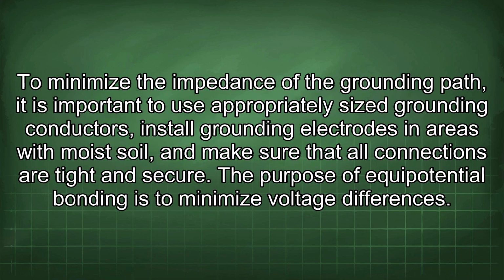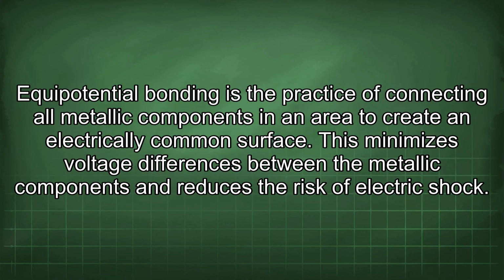To minimize the impedance of the grounding path, it is important to use appropriately sized grounding conductors, install grounding electrodes in areas with moist soil, and make sure that all connections are tight and secure. The purpose of equipotential bonding is to minimize voltage differences. Equipotential bonding is the practice of connecting all metallic components in an area to create an electrically common surface. This minimizes voltage differences between the metallic components and reduces the risk of electric shock.